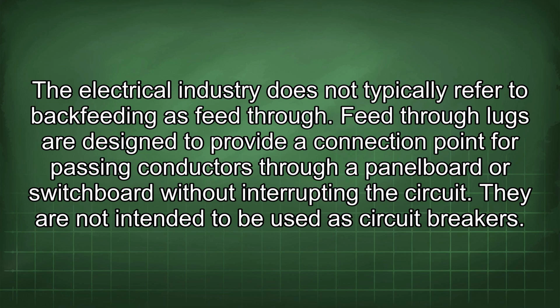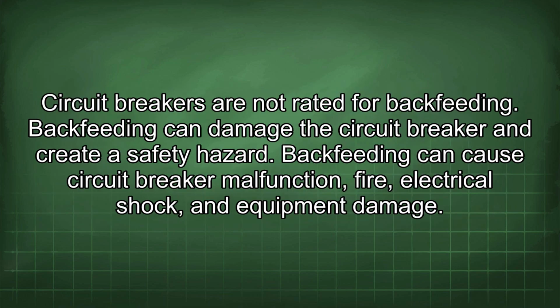Feed-through lugs are designed to provide a connection point for passing conductors through a panel board or switchboard without interrupting the circuit. They are not intended to be used as circuit breakers. Circuit breakers are not rated for backfeeding. Backfeeding can damage the circuit breaker and create a safety hazard. Backfeeding can cause circuit breaker malfunction, fire, electrical shock, and equipment damage.